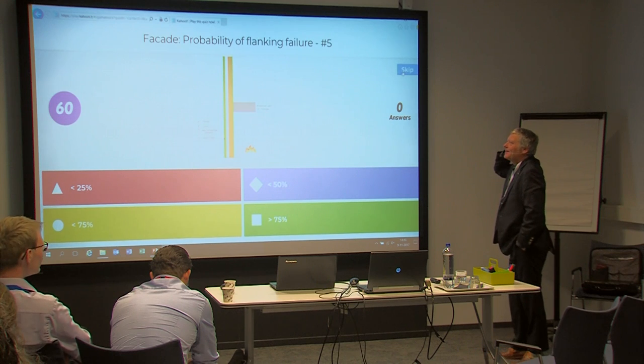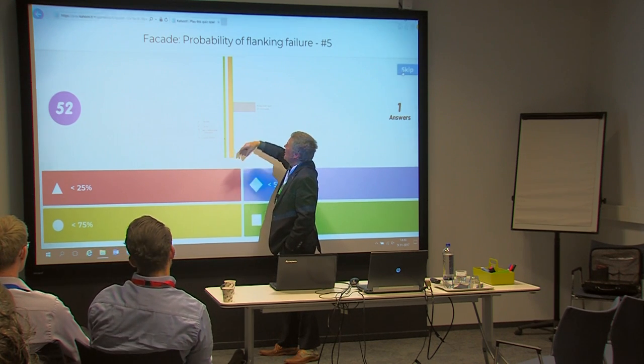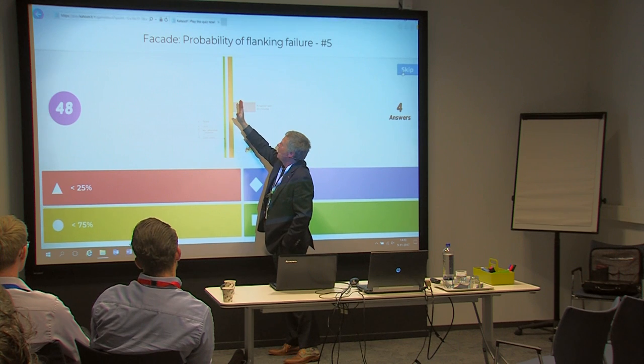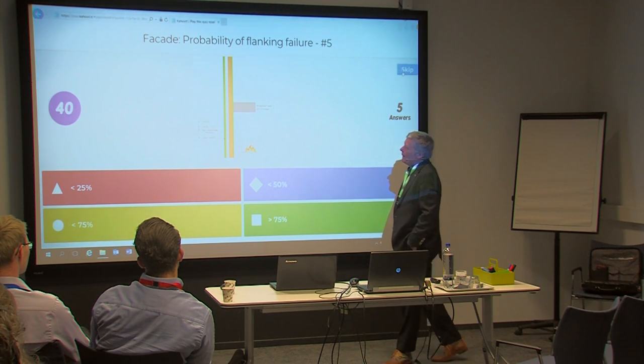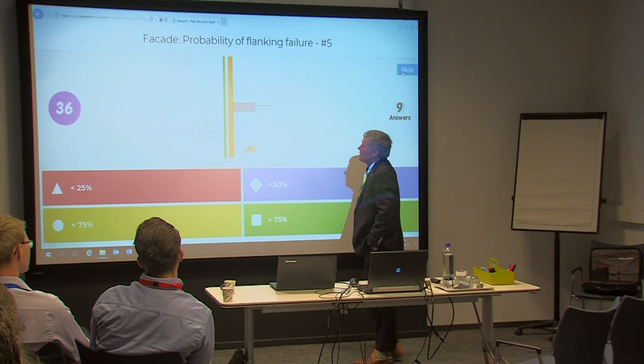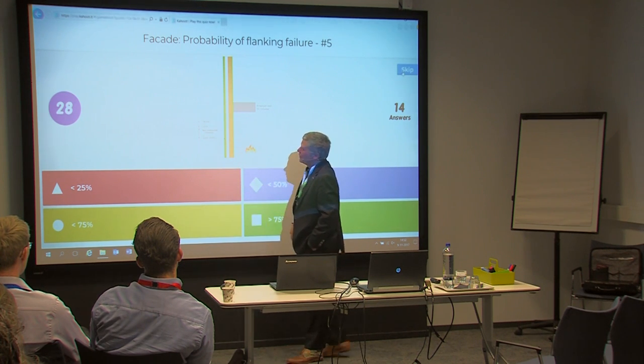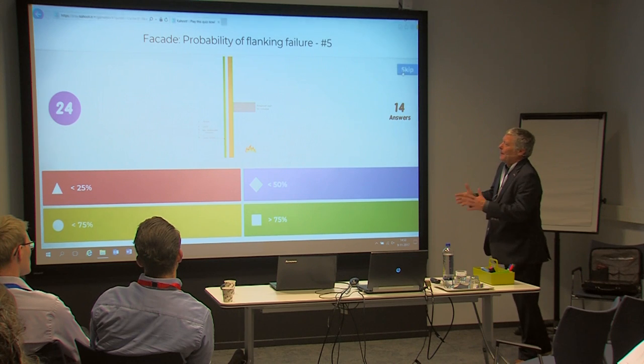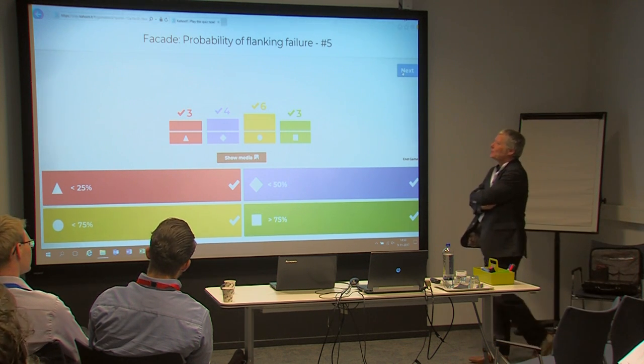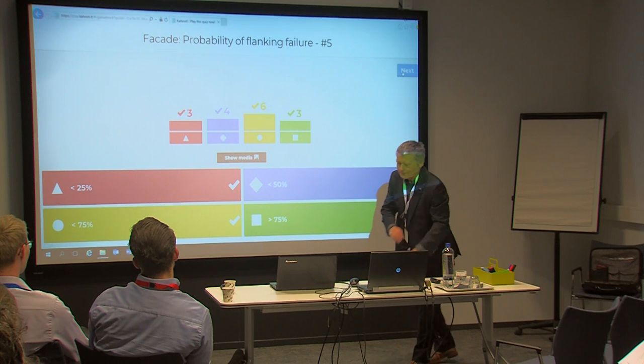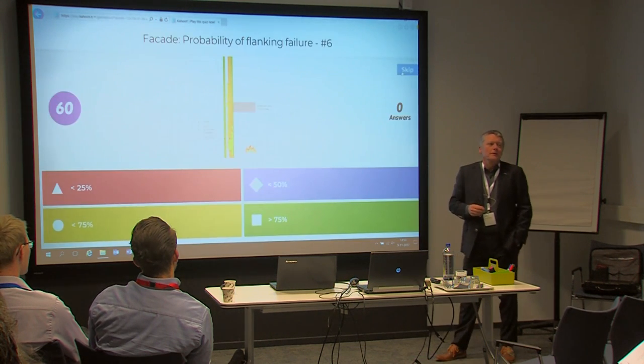The fifth facade detail introduces a cavity in the facade: non-combustible material layers, a cavity, the firewall connecting to the facade, and the facade running along the firewall. Here there are different transport mechanisms — conduction through cladding or material, and also possible convective transport through the cavity. Results show a lot of spread in expert opinion, which is understandable because the cavity introduces additional complexity and uncertainty.